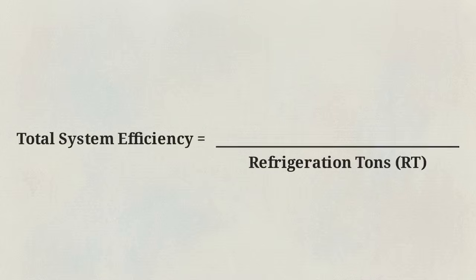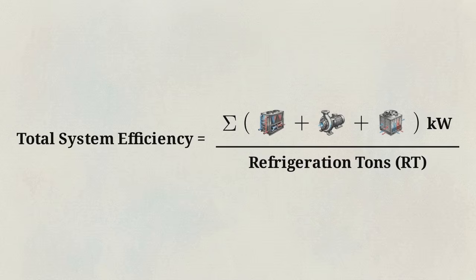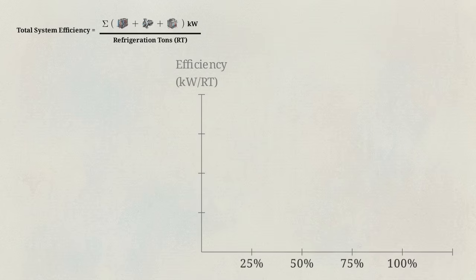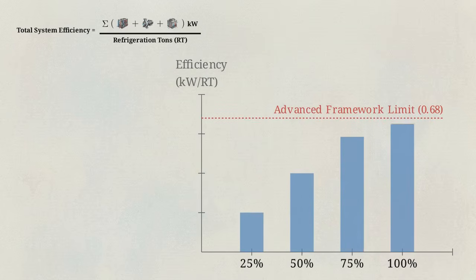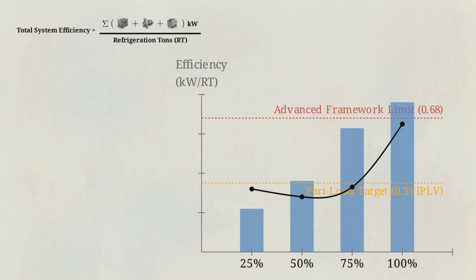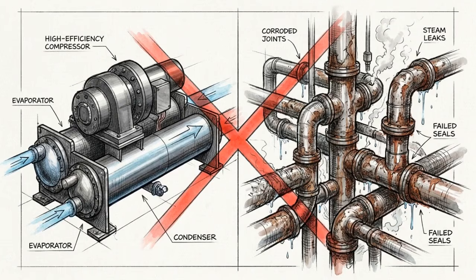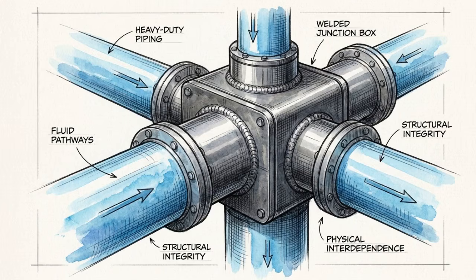The total system efficiency formula divides the combined power of all chillers, pumps, and towers by refrigeration tons. Advanced frameworks require the ecosystem to hit under 0.68 kilowatts per ton. This target must hold during part load operation. Redundant systems rarely run at full load, so the integrated part load value must remain below 0.35. Procuring high-performance individual machines yields no benefit if the integrated thermodynamic boundary fails to meet these total system efficiency targets. The entire chain must perform as one.